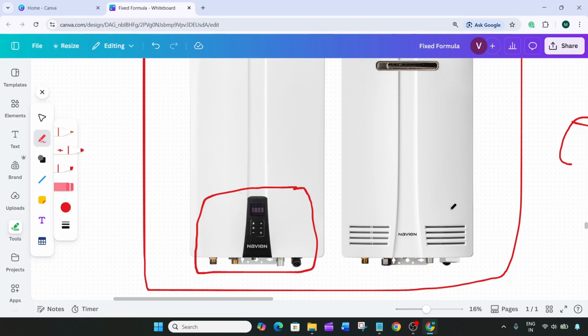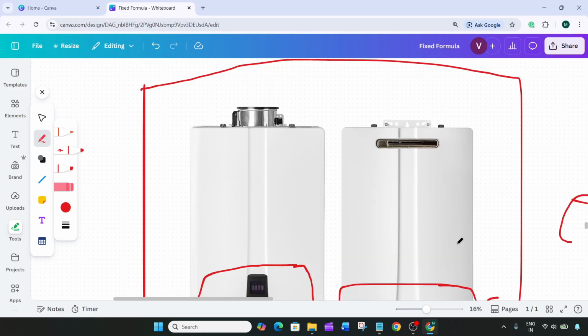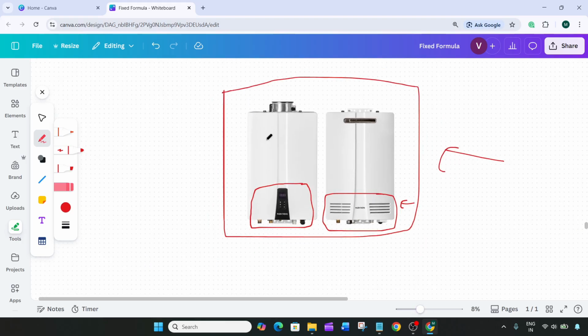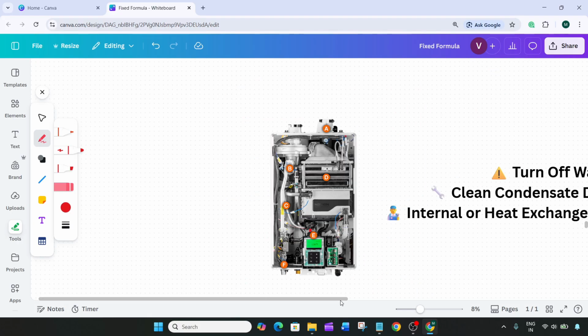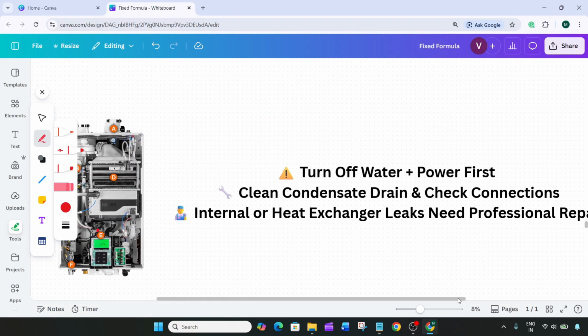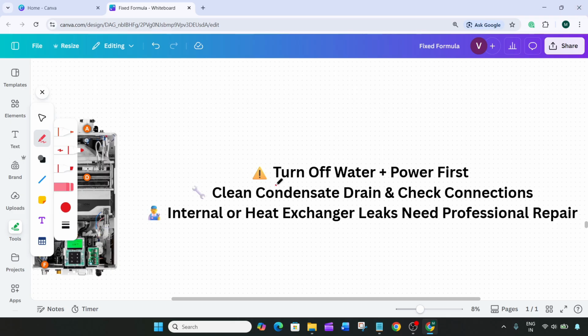Bottom leaks usually come from a few common areas. One of the most frequent causes is a clogged or damaged condensate drain or trap. Dirt buildup or a worn O-ring inside the trap can allow water to escape underneath the heater. Loose or corroded water supply connections can also cause slow leaks over time, especially in hard water environments.